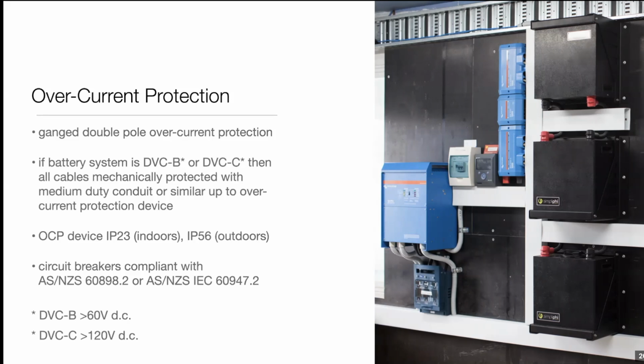There are some extra requirements too for overcurrent protection devices. They need an IP rating of IP23 for indoors and IP56 for outdoors. So just make sure your product actually has the correct IP rating. And there's a specification for any circuit breakers that you use on a battery system for overcurrent protection.